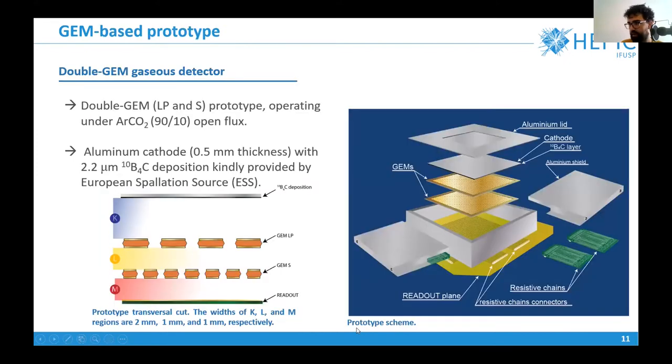In yellow we have the tracks of the ions produced by this multiplication. In our detector we use two microstructures, two GEMs with different pitch sizes. The large pitch one has 280 micrometers between every two holes and the standard one has 140 micrometers between every two holes. We use a deposition at the cathode of our detector, a boron-10 carbide deposition 2.2 micrometer thickness.